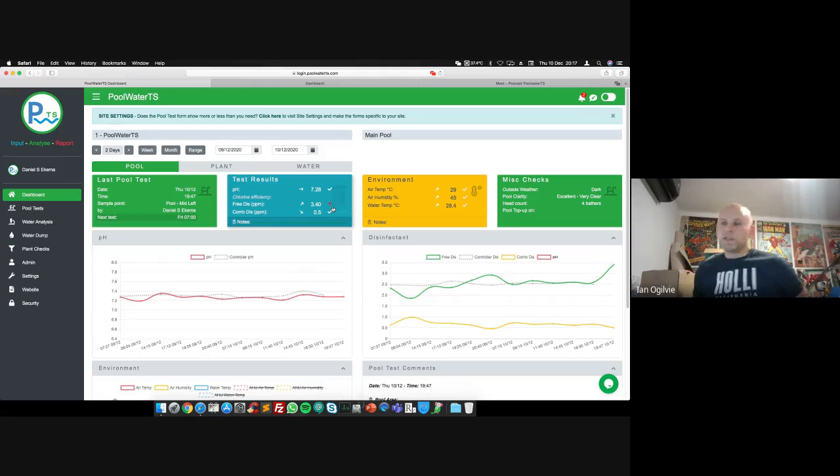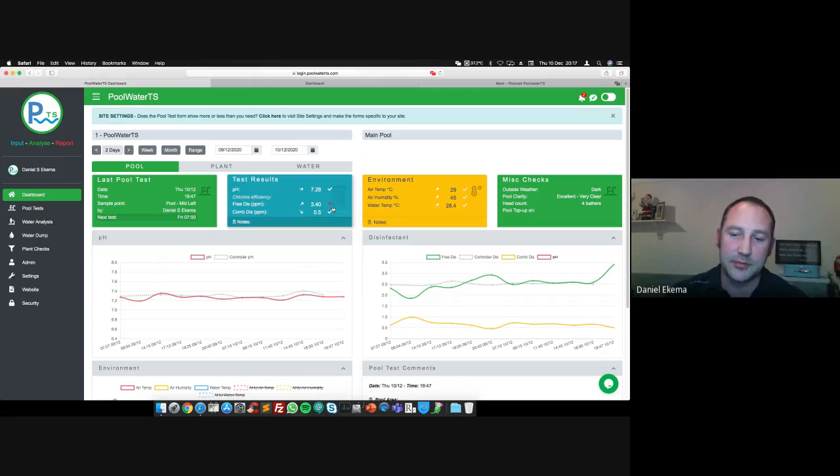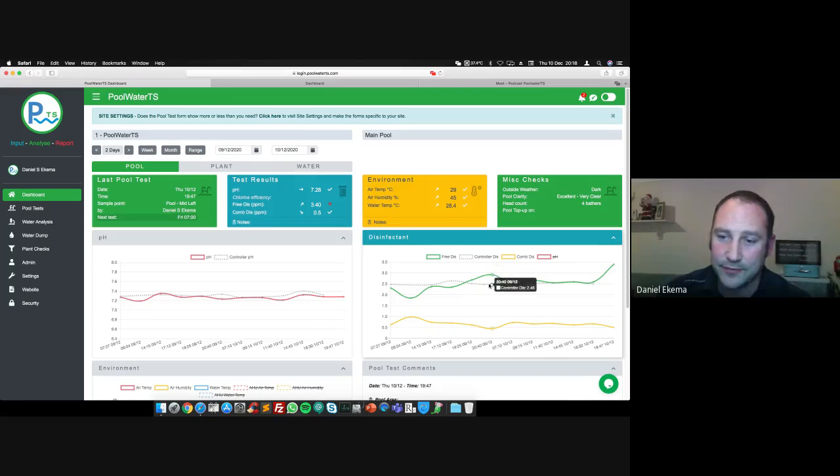So we can see there, Dan, we've got a red line on your pH, a green line on your free chlorine level, but also this grey dashed line for the controller unit as a double read, so you can map where the lines are and see them being level. Exactly, yeah. In terms of knowing how the plant room's running, being able to see whether the controller is actually matching what the results are showing is quite key to know that it's dosing properly. For example, in the scenario on the screen at the moment, you notice the controller reading is quite different from the readings here and here.